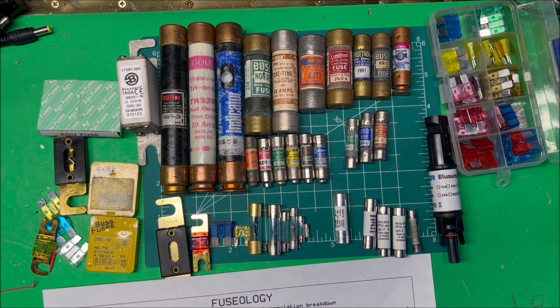Now, the motor should be fused with a time delay fuse rated at 175% of the motor's full load amps, or a non-time delay fuse at 250%. Motors have overload protection in them. Overload heaters in there are magnetic or thermal, and they protect against overloads, and the fuses are protecting against a short circuit. Now, branch circuits: when you calculate the size of branch circuit you need, you have to add up all the non-continuous loads plus 125% of the continuous loads to do your calculations for a circuit.